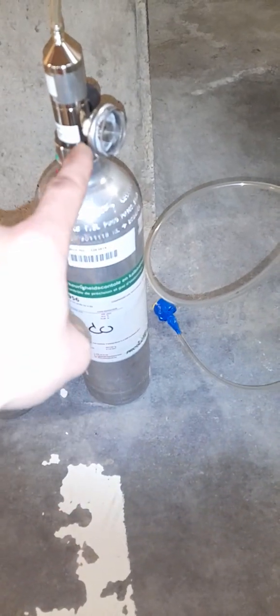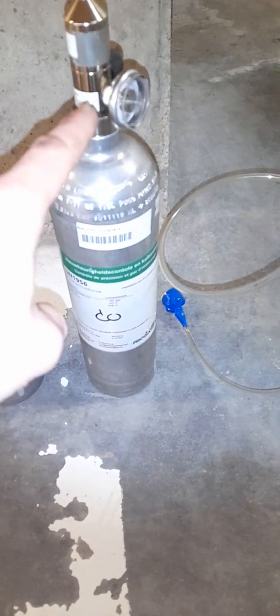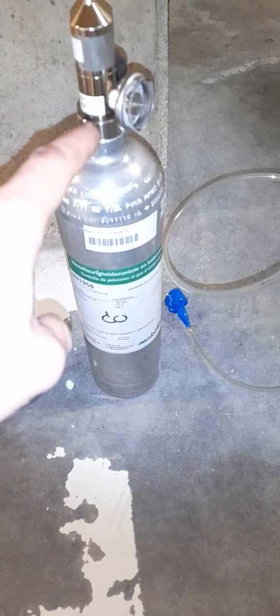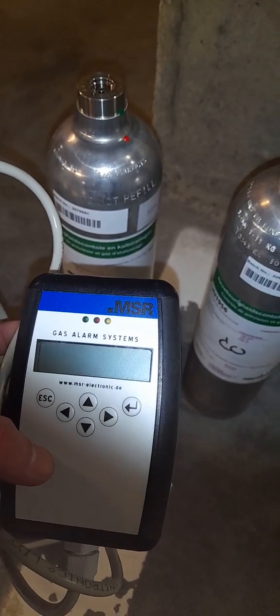Okay, so first things first, to calibrate the CO sensor, we're going to need two bottles, a zero and a CO. On top of that, we're going to need this one, which is going to do the calibration. I'm going to show you how to take it off. You're also going to need a calibrator, an MSR meter, and a flat screwdriver. I don't know what a flat screwdriver is, it's not a Phillips one. There you go, one of these.